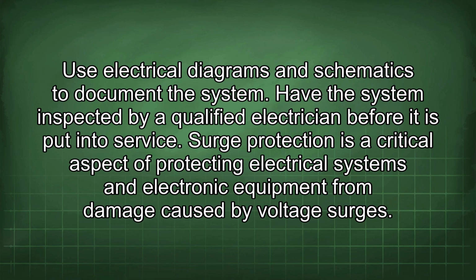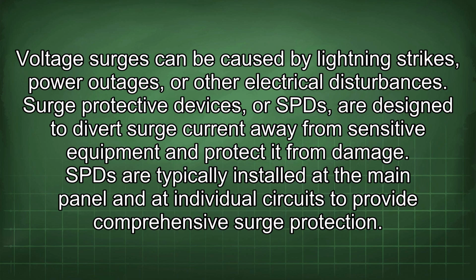Surge protection is a critical aspect of protecting electrical systems and electronic equipment from damage caused by voltage surges. Voltage surges can be caused by lightning strikes, power outages, or other electrical disturbances. Surge protective devices, or SPDs, are designed to divert surge current away from sensitive equipment and protect it from damage. SPDs are typically installed at the main panel and at individual circuits to provide comprehensive surge protection.